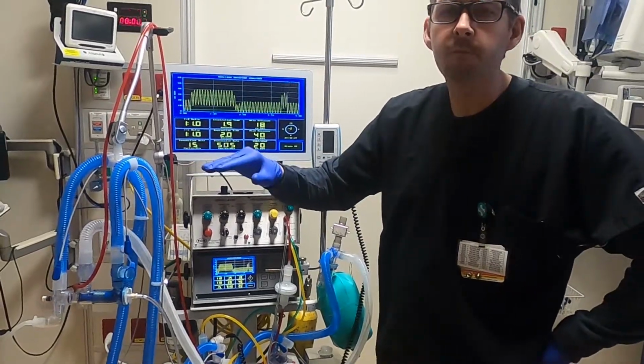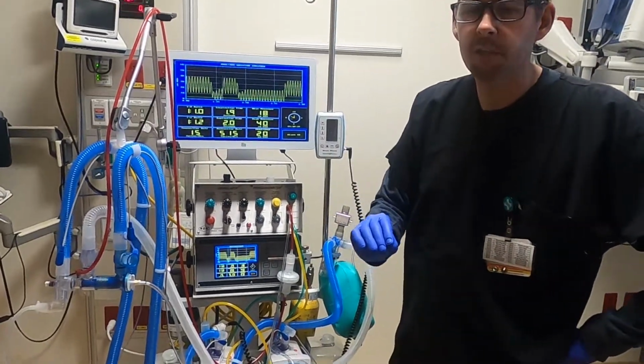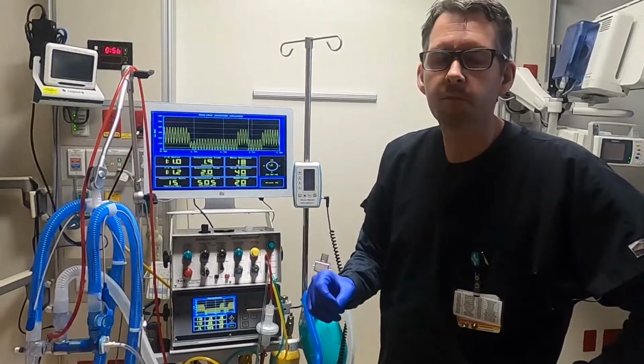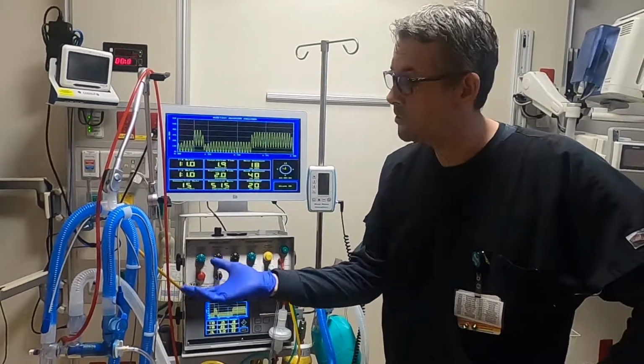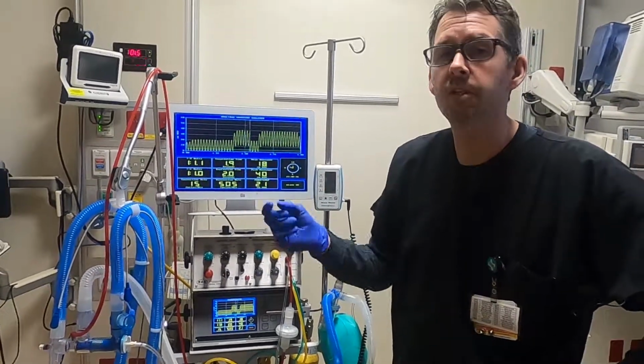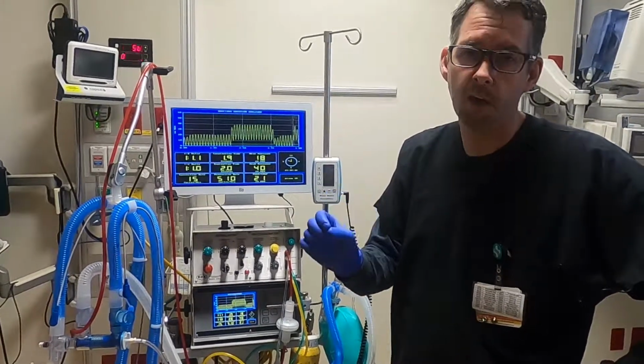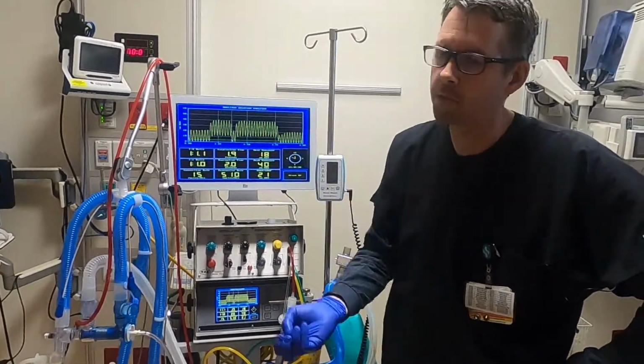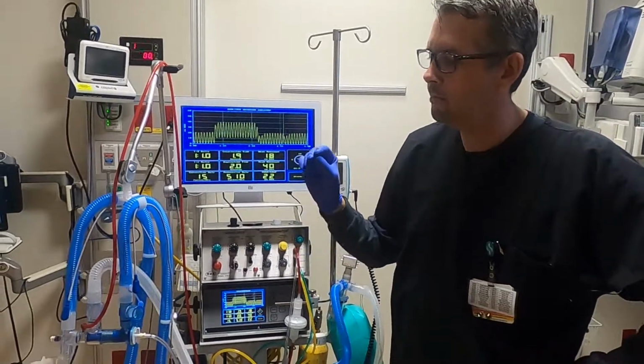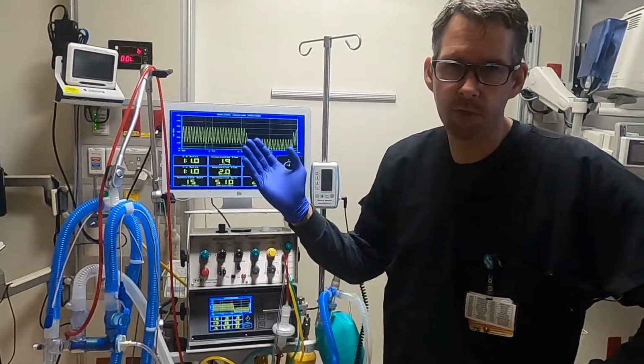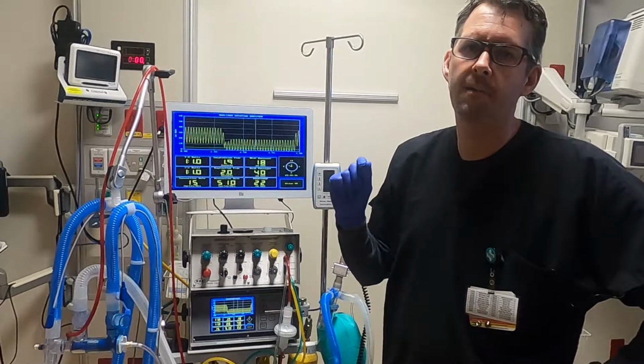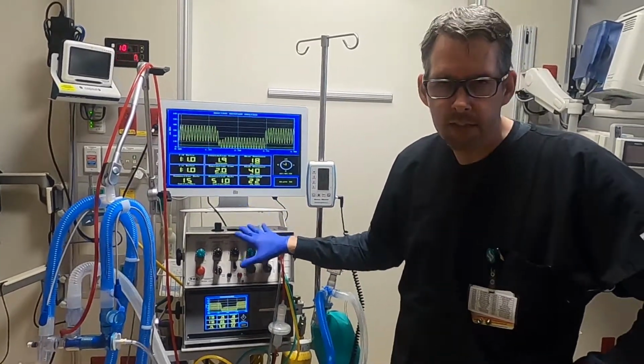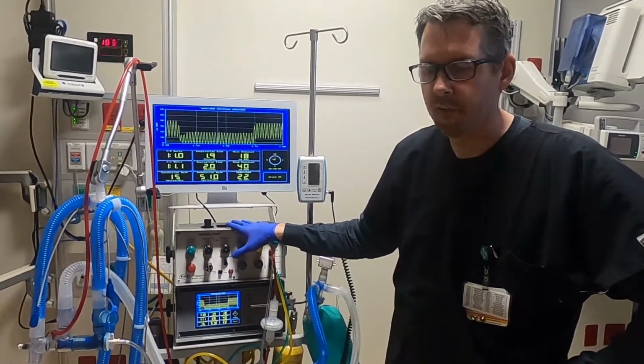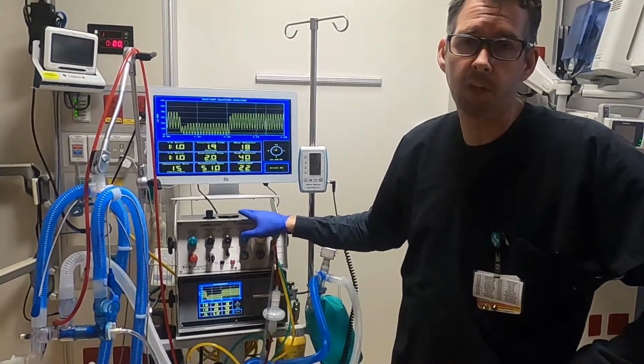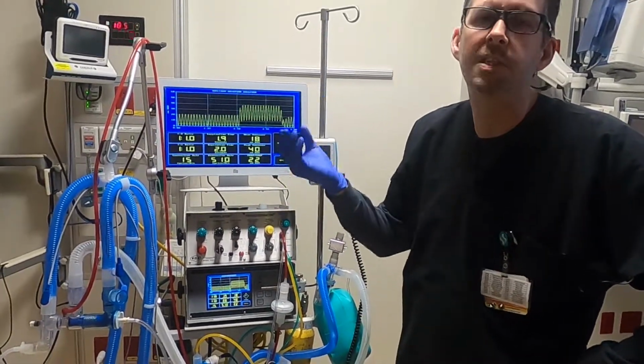If you see a decreased chest movement, suction the patient. If you're getting a lot of secretions, one of the ways this machine will help get rid of even more secretions is to deflate the ET tube cuff a little bit, and it'll actually pull the secretions right out through there. That will also get rid of CO2, so that's one of the things you can do if you're having high pressures and high CO2s, and you're already on high pressures on your ventilator: you can deflate the cuff a little bit and let some of that CO2 escape.